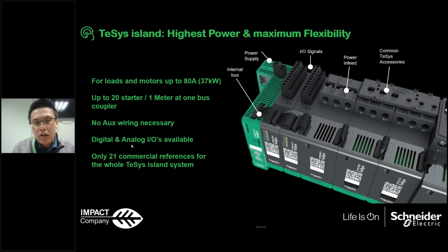And then digital and analog I/O is also available. You will see that we have analog modules with 2 inputs and 1 output, and digital modules with 4 inputs and 2 outputs, so that you can bring all the sensor inputs to the system to set different thresholds for alarming or to do the autonomous control. All the analog or digital signals can feed back to the system, and then you can do what you want to do. In terms of the reference level, it is very simple. We only have about 21 references, so it's kept simple for customers for selection or configuration.